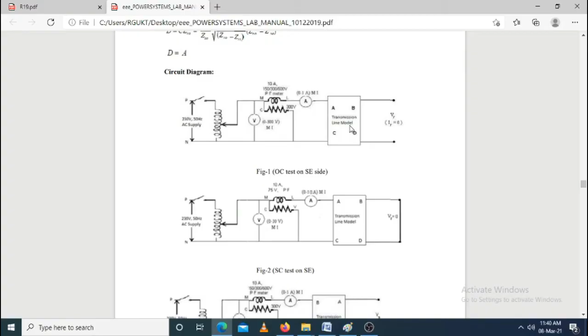We are applying the rated current, which generally is 5 amps only. So the maximum is 5 amps. The voltage is 0 to 30 volts, which we apply with the help of the auto transformer. The maximum current will be close to 5 amps. This is the rated current. Voltage divided by current is the impedance. Here, it is the sending end impedance whenever the receiving end is short circuited. So we are calculating ZSO and ZSS.